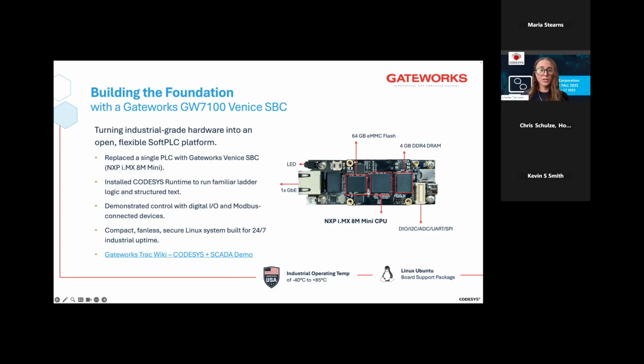Our customer installed the CODESYS runtime on the board, turning it into a soft PLC, a software-based programmable logic controller that could execute the same ladder logic, structured text, and function blocks that engineers were already familiar with. In CODESYS, they recreated the existing control logic, starting simple: reading digital inputs from push buttons, toggling outputs to drive LEDs and relays, and managing a few Modbus connected I/O devices.